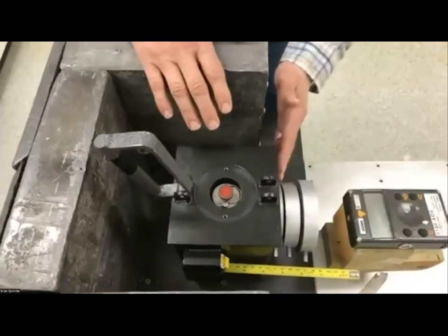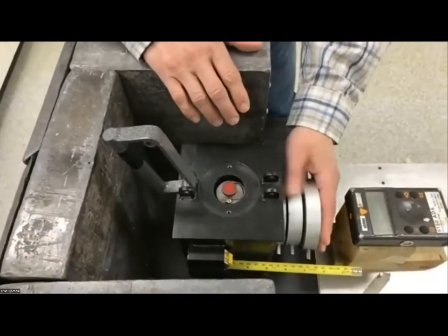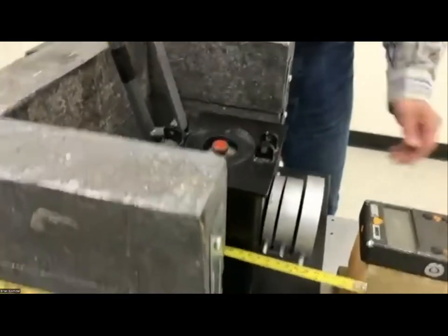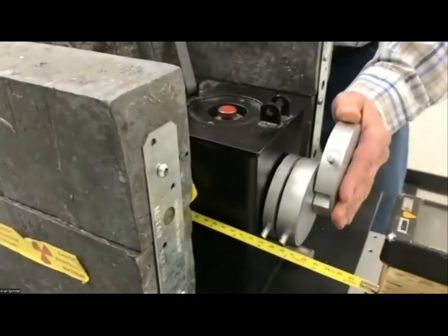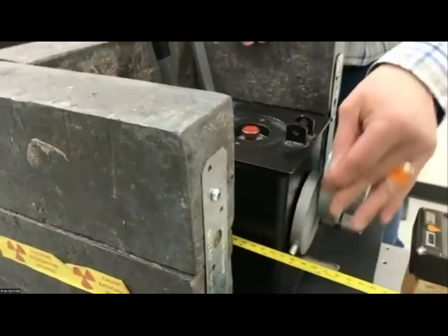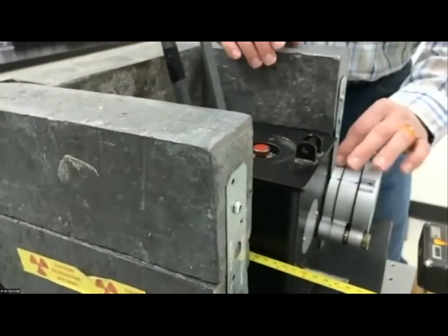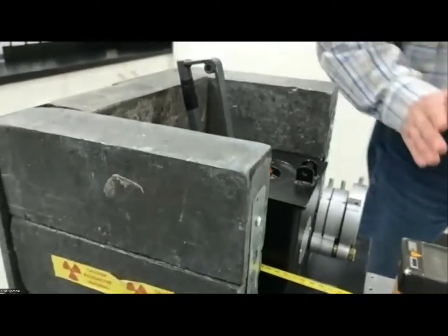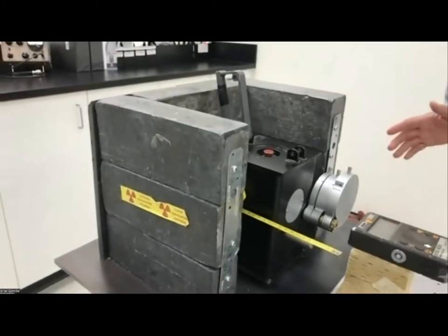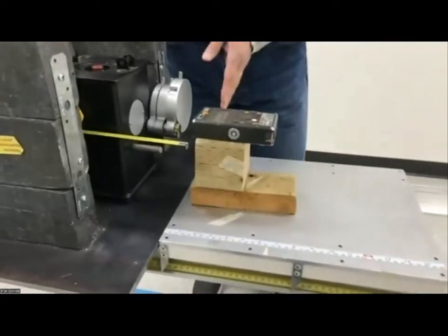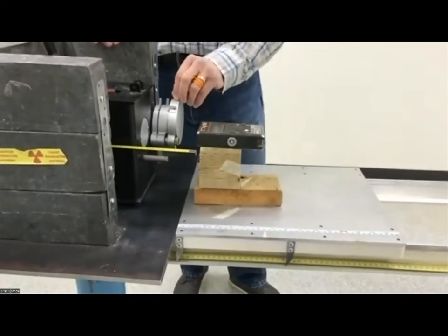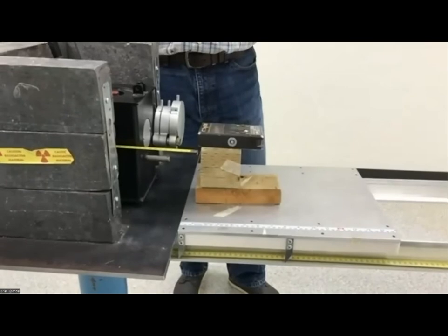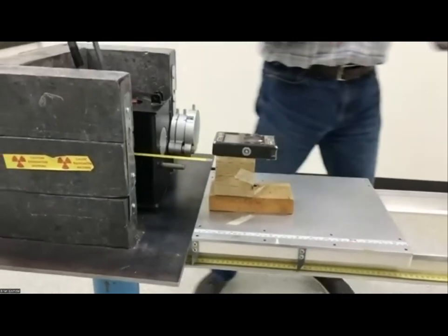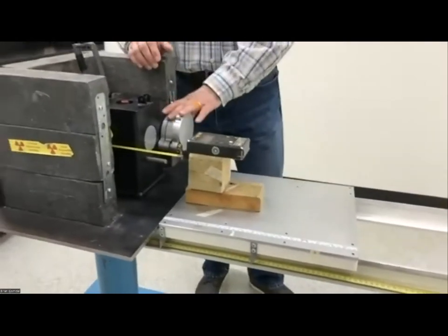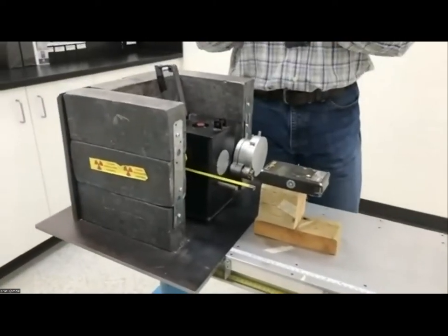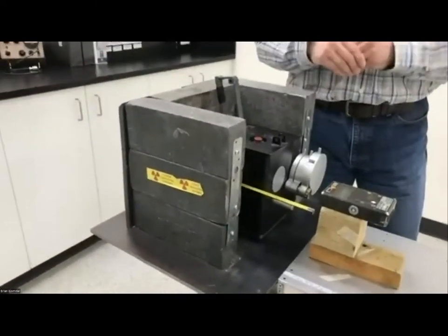On the front here, and we'll show you the calibration, we have these attenuators, which are really nice to have. There's a 0.1 attenuator and a 0.25. When we're exposing instruments, we can move the instrument back and forth on this rail system, or we can find a sweet spot, and then use attenuators to attenuate the beam without having to move the instrument. Some calibrations require us to move the instruments around, but most times we can use these attenuators to flatten and reduce the beam to do the calibrations.